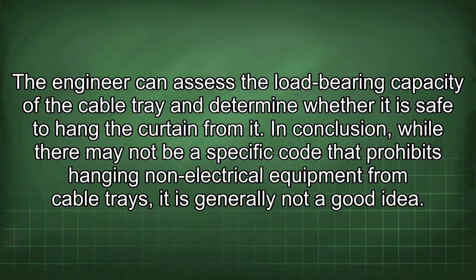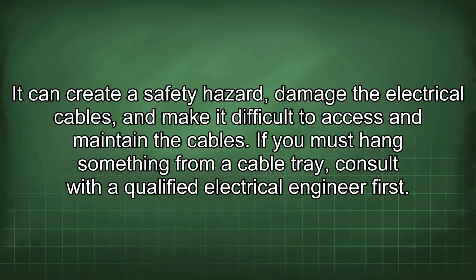curtain from it. In conclusion, while there may not be a specific code that prohibits hanging non-electrical equipment from cable trays, it is generally not a good idea. It can create a safety hazard, damage the electrical cables, and make it difficult to access and maintain the cables. If you must hang something from a cable tray, consult with a qualified electrical engineer first.